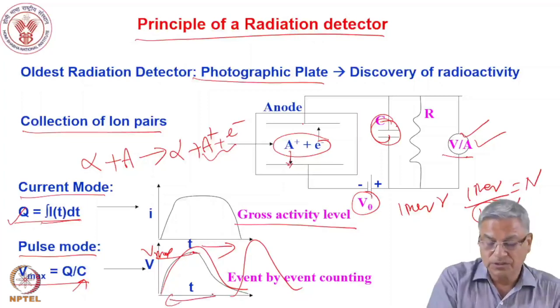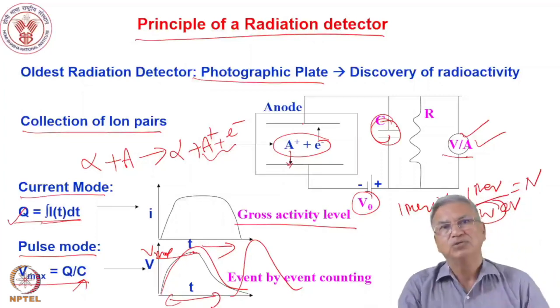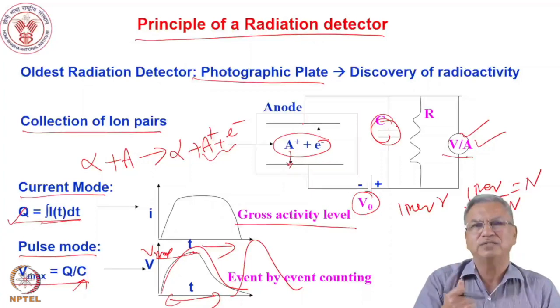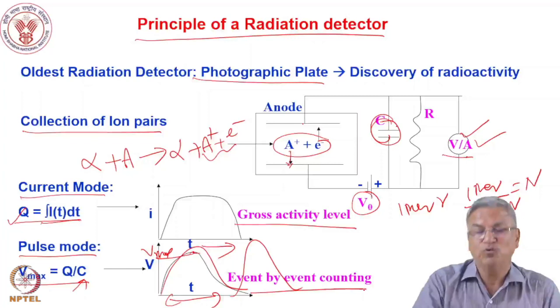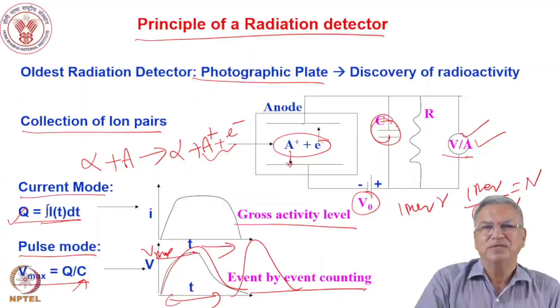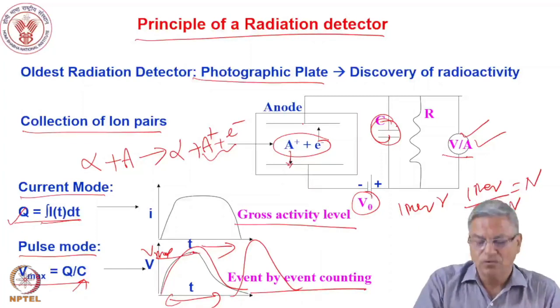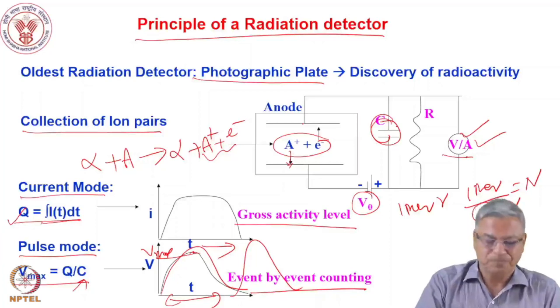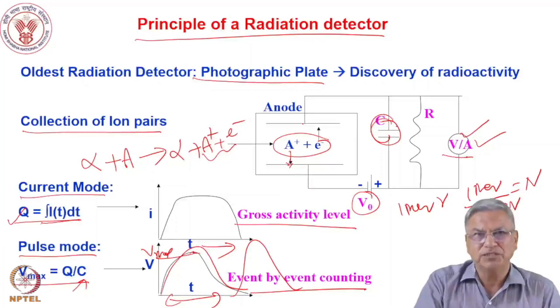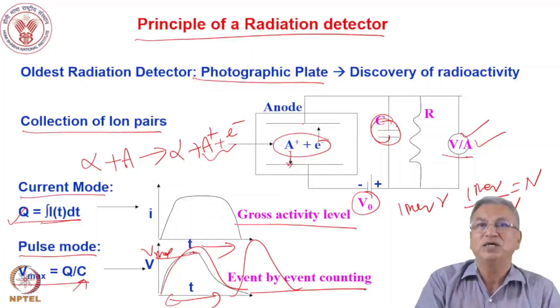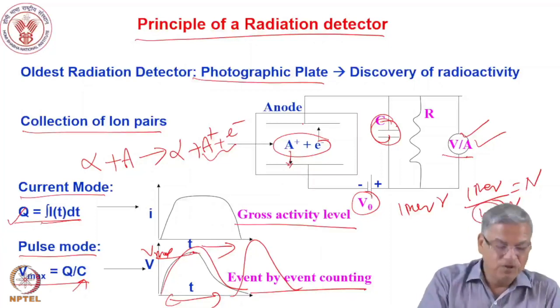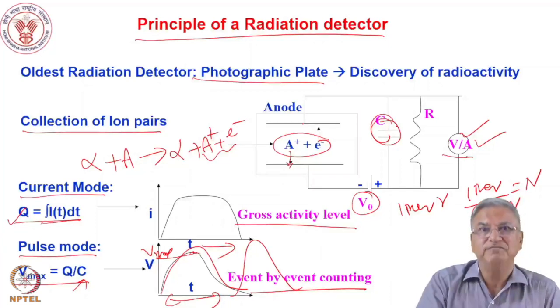We will discuss about the dead time. Different individual pulses are counted in the detectors in pulse mode, and that pulse mode is used for event-by-event counting — each decay can be counted separately. Detectors are operated in current mode and pulse mode. Some detectors are used in current mode, like survey meters, where you are interested only in gross activity level. Whenever you want to measure each event separately, you use pulse mode.